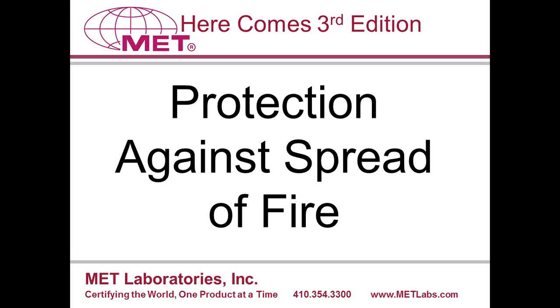Now let's talk about changes to the fire hazard design requirements. 6.10.10 has requirements for eliminating or containing the spread of fire. You can eliminate the risk of fire with a limited energy circuit, or you can limit the spread with a fire enclosure and appropriately flame-rated components. Whenever you have a limited energy circuit, you do not have to meet the stringent enclosure or flammability requirements.